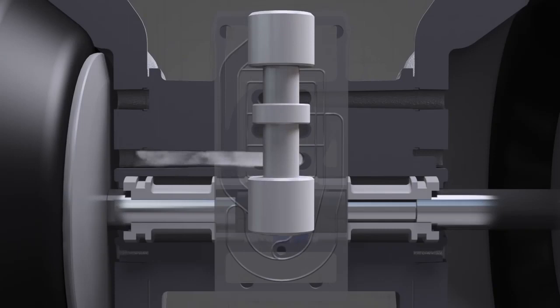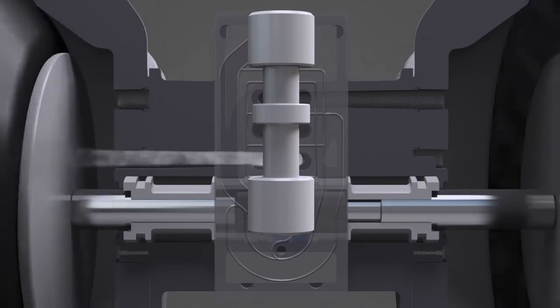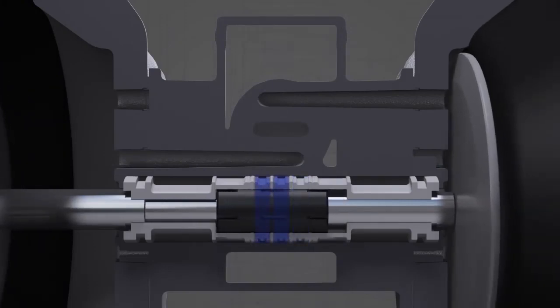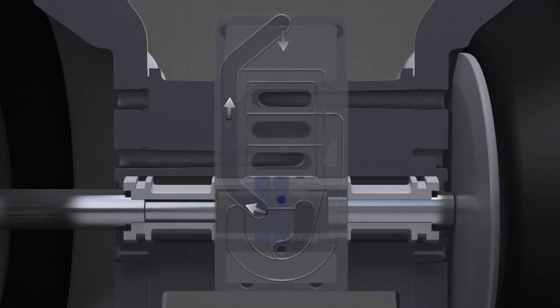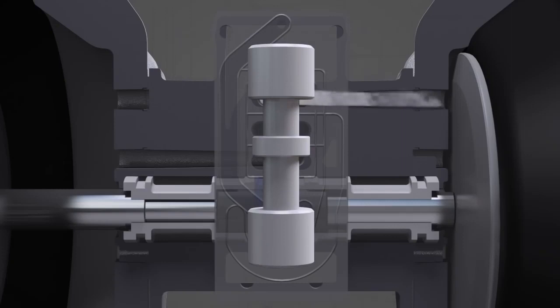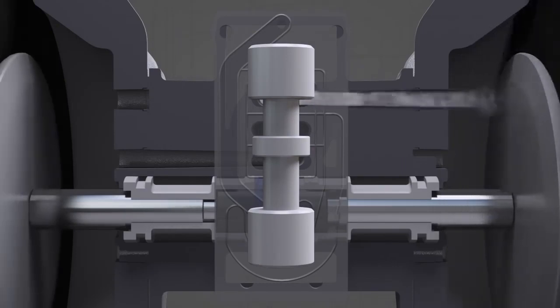This causes the left diaphragm to pressurize and the pilot valve to begin moving left. When the pilot air valve travels far enough to the left, chamber three connects to chamber two, and the air moves the main air valve downward. This causes the right diaphragm to pressurize and the pilot valve to begin moving right.